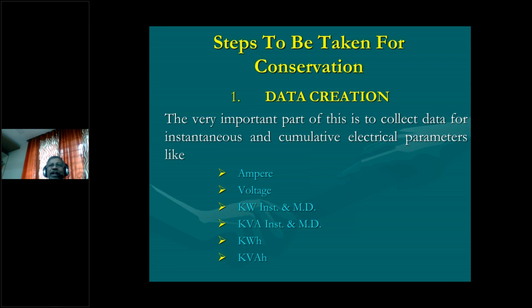So in electrical parameter, active, reactive, and apparent power, that is kW, kVA, RKVA, are covered in instantaneous parameter. Another is ampere, voltage, frequency. kVA, voltage ampere. Kilo means we consider in industry it is kilovolt. So kW, kVA, RKVA, that is lead, lag, ampere, voltage, frequency. These are instantaneous parameter. And cumulative parameter means kWh, kVAh, RKVAh, then RKVAh lead and lag. Now these are the new parameters that are introduced, that is lead and lag reactive power. So these are our different parameters.